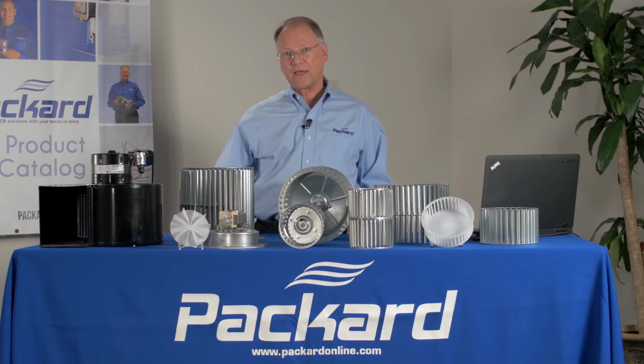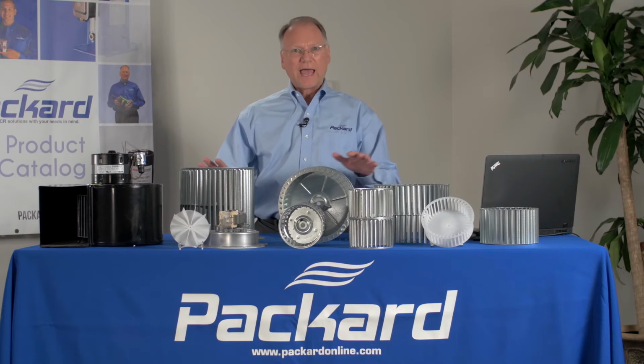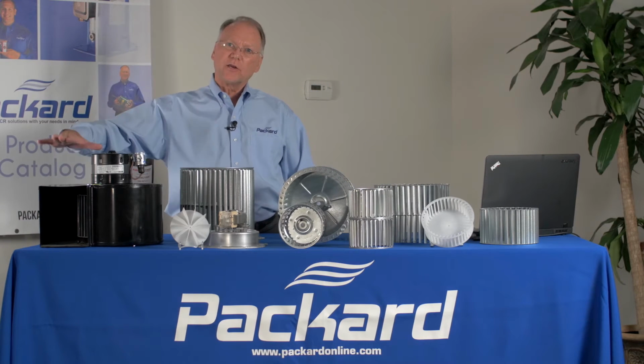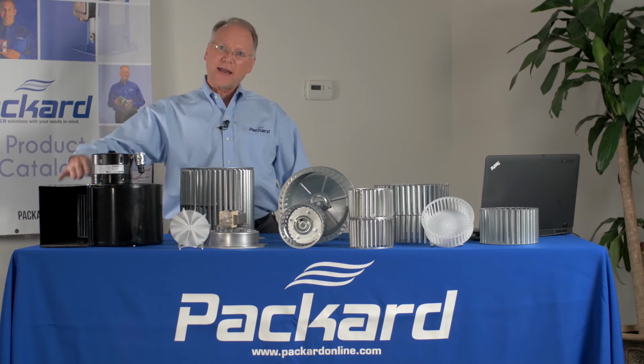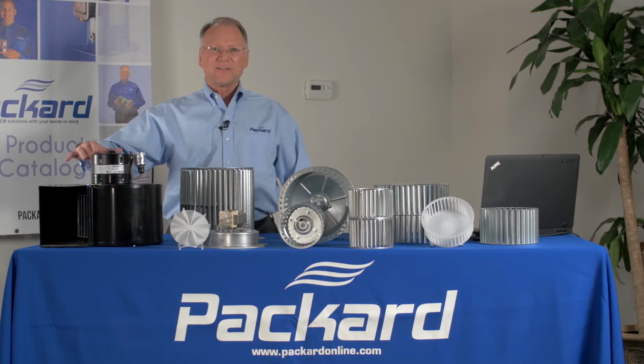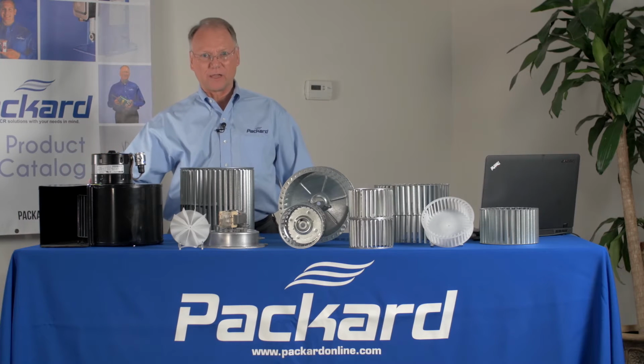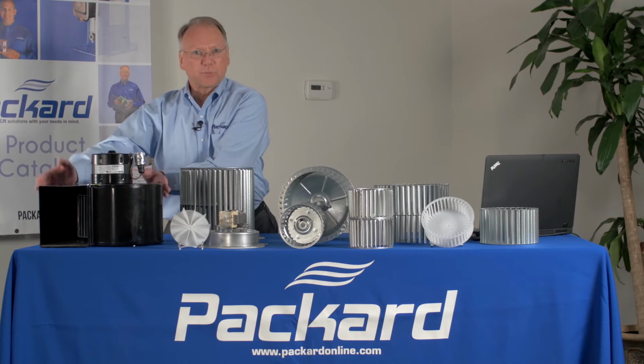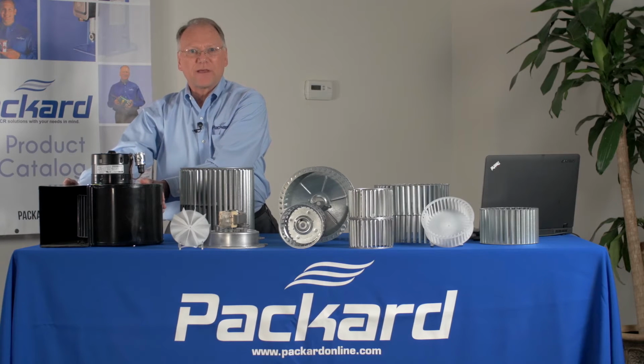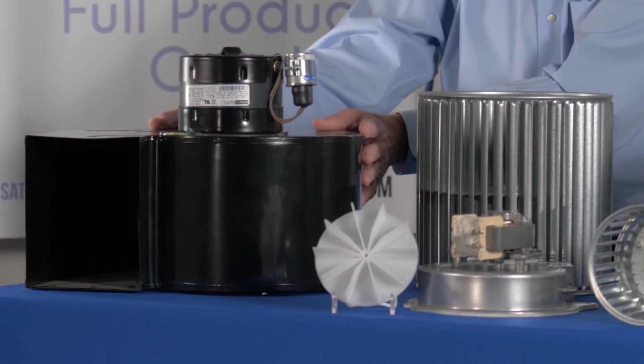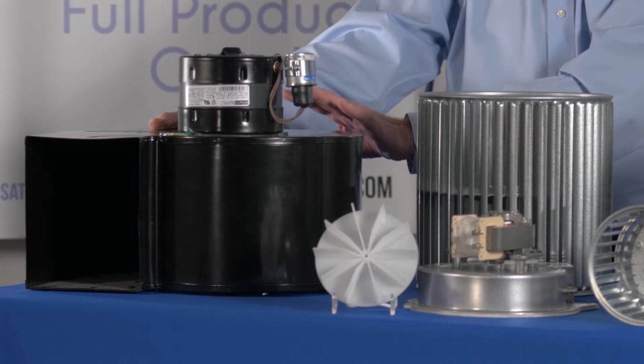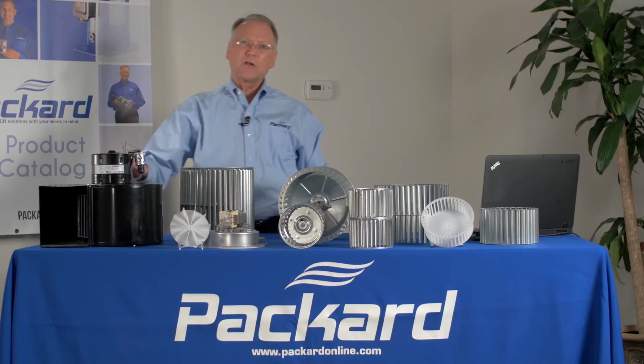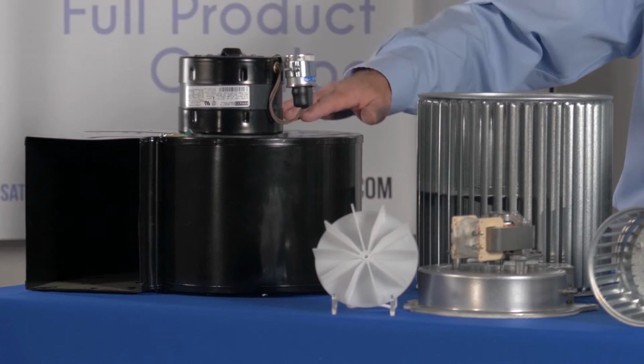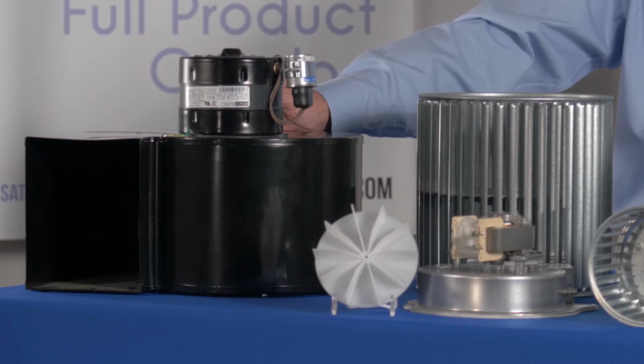When looking at a replacement for a particular wheel, you'll notice that wheels are not identified in terms of CFM, as a fan blade may be. The reason for that is a wheel has to be matched with the housing in order to give you the proper air performance. Without the housing, you cannot identify the CFM at any given static level. If you look at a complete blower package, it will be identified with CFM, which is cubic feet per minute of air, as well as static pressure, which is normally identified in inches of water column.